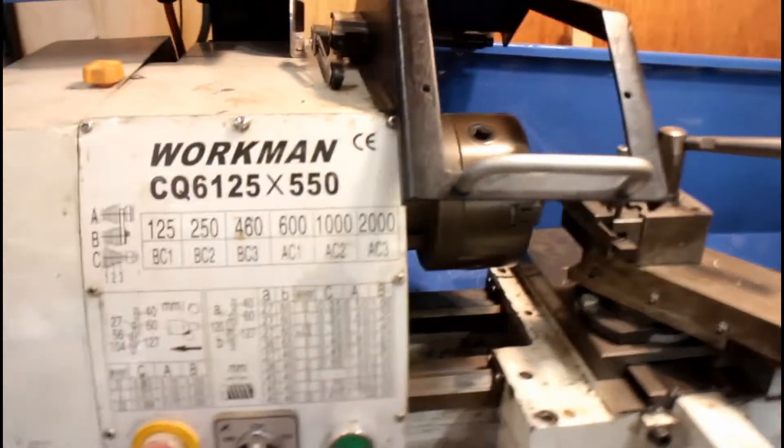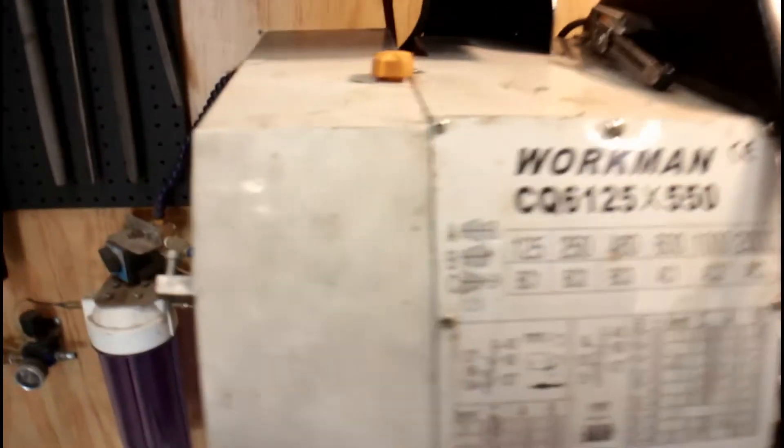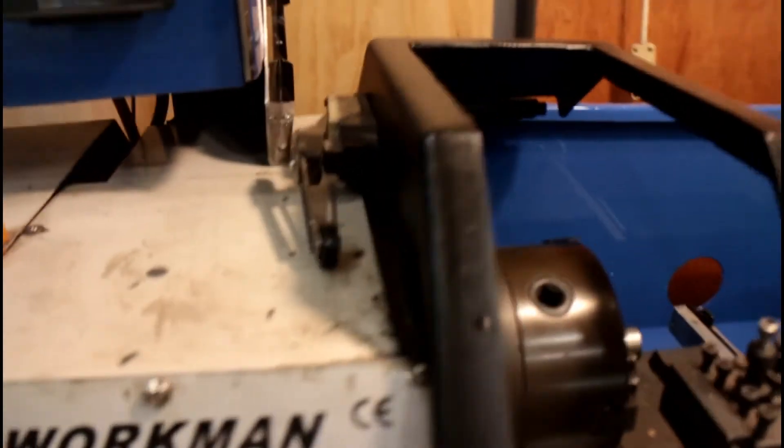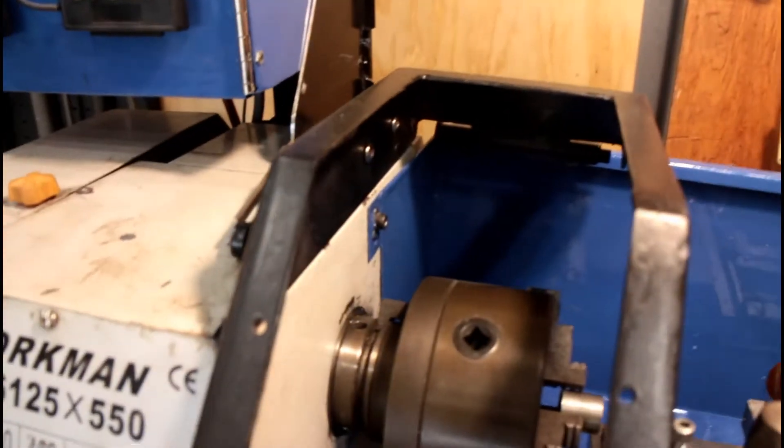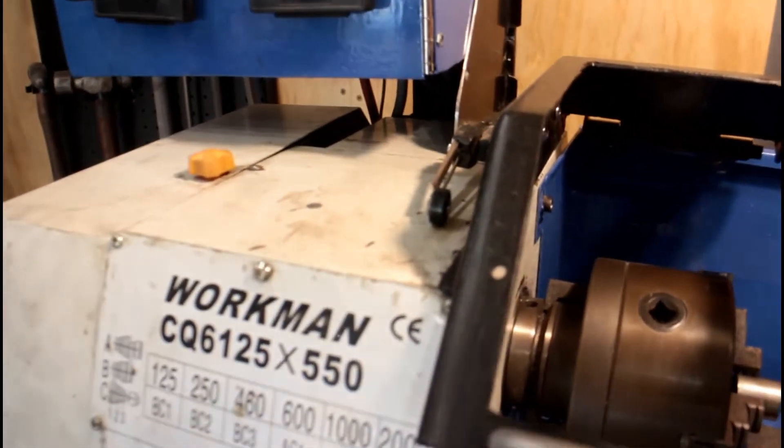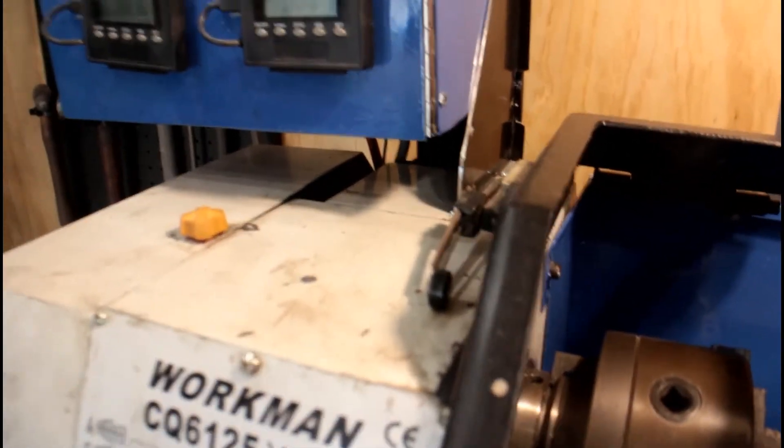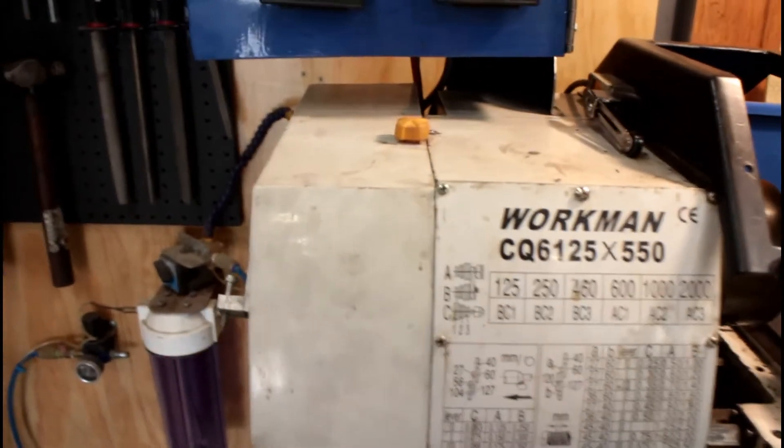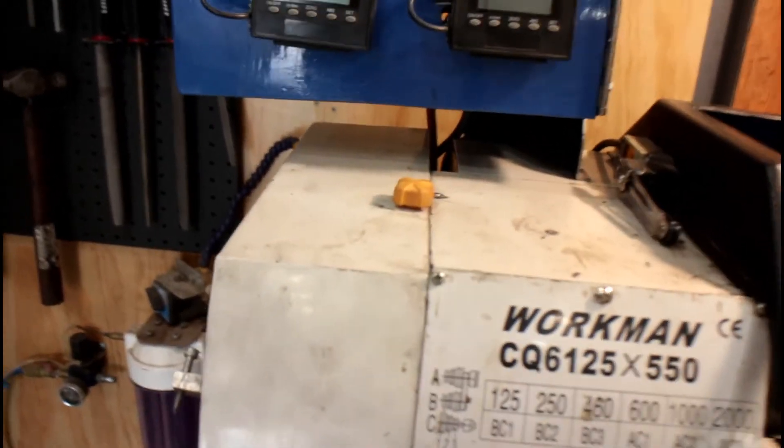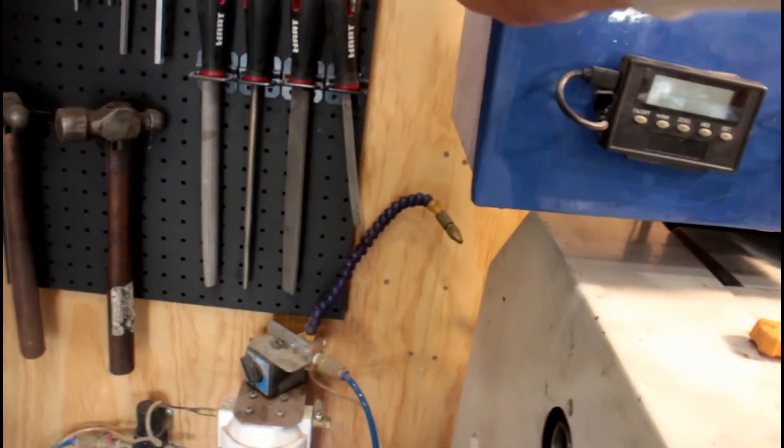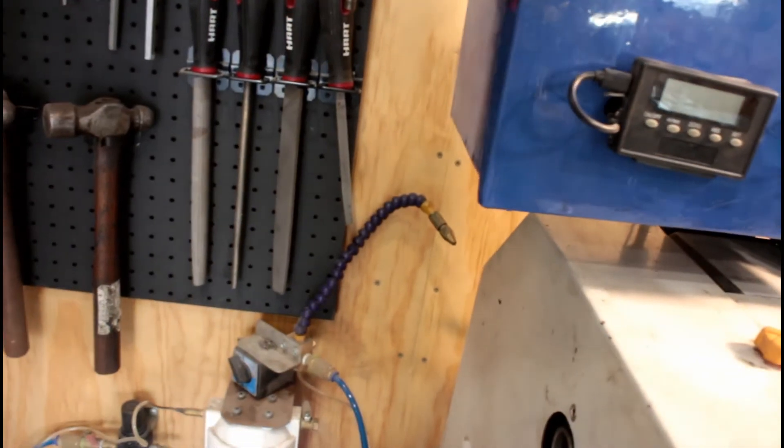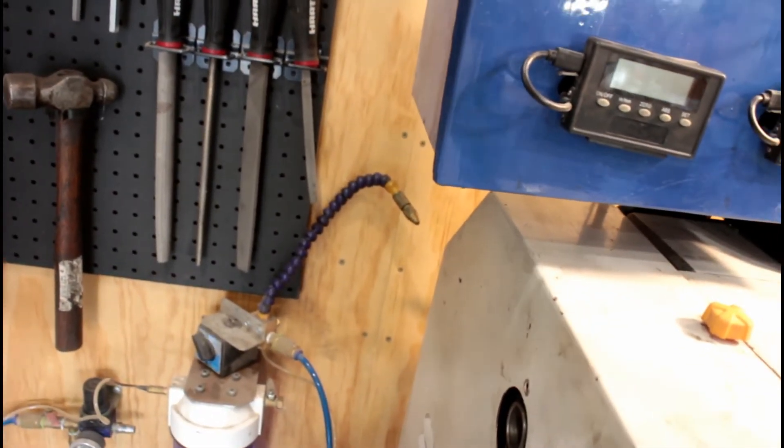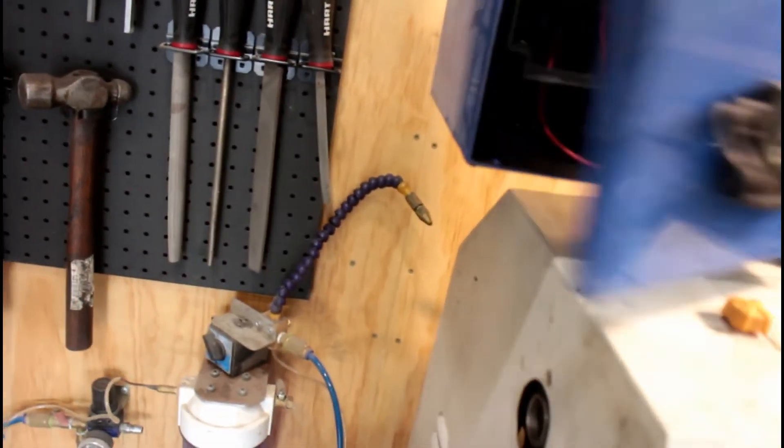If you try to control this by using the output from the VFD that goes to the motor, you will ruin the motor, the VFD, or both. They're not designed to work that way. Let's just quickly open this. My battery is going to go flat.